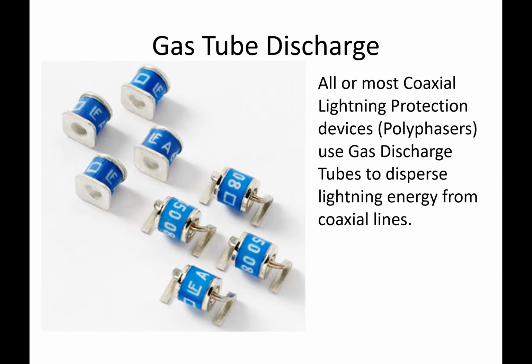Some radio amateurs with a lot of towers make these homemade arc devices. Basically it's a welded device in contact with the tower and another welded device in contact with the ground rod, in very close proximity to each other, designed to arc over when there's high voltage present from the tower to ground. It acts like the same thing as a gas tube discharge device. These are simply a more convenient way to protect your coax feed lines from high voltage surges and lightning discharges. Any other questions? This is K1RCT.